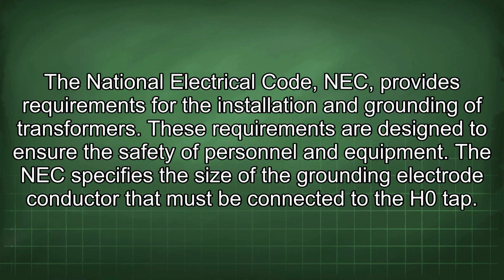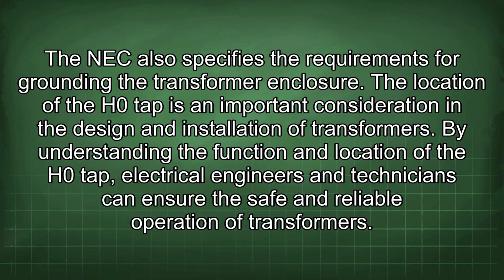The National Electrical Code, NEC, provides requirements for the installation and grounding of transformers. These requirements are designed to ensure the safety of personnel and equipment. The NEC specifies the size of the grounding electrode conductor that must be connected to the H0 tap. The NEC also specifies the requirements for grounding the transformer enclosure.